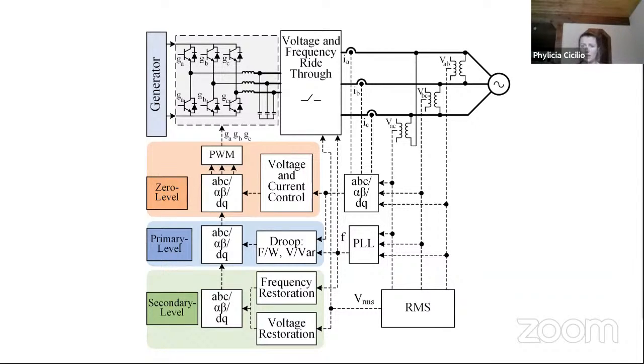These control loops increase in time step, where the innermost control loops control those voltage and current waveforms. Then there's a power sharing control, such as droop, and then frequency and voltage restoration loops that are associated with voltage and frequency stability. Additionally, there is the protection trip function seen in the voltage and frequency ride-through block, which either trips or leaves the generator on during voltage or frequency swings. These are like disturbances such as generators or loads tripping on or offline, large generators or loads tripping offline, or faults happening in the system.